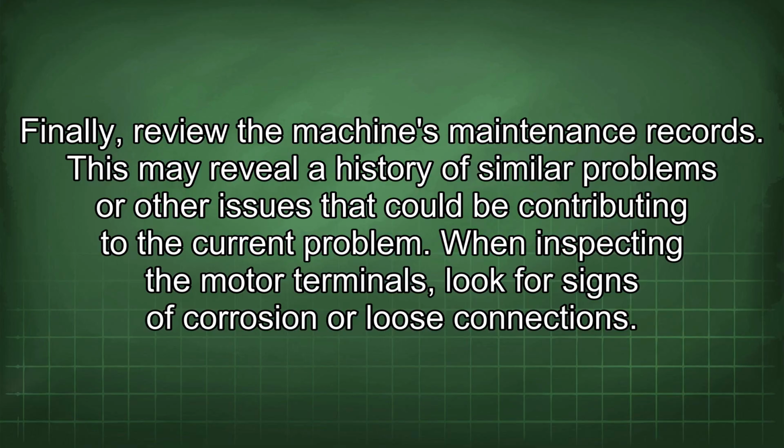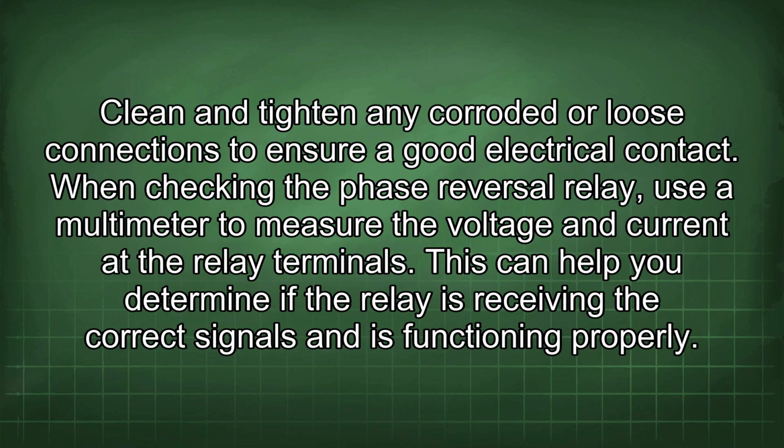When inspecting the motor terminals, look for signs of corrosion or loose connections. Clean and tighten any corroded or loose connections to ensure a good electrical contact. When checking the phase reversal relay, use a multimeter to measure the voltage and current at the relay terminals. This can help you determine if the relay is receiving the correct signals and is functioning properly.